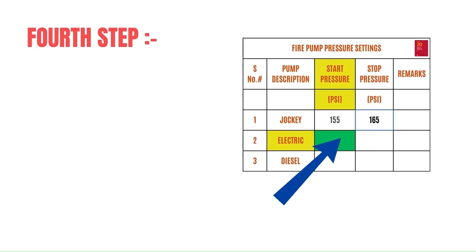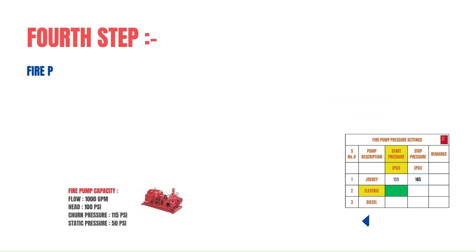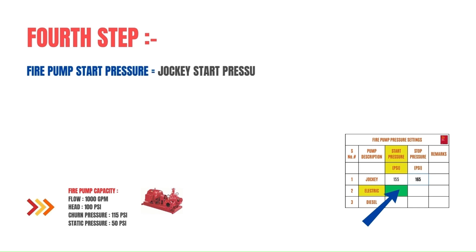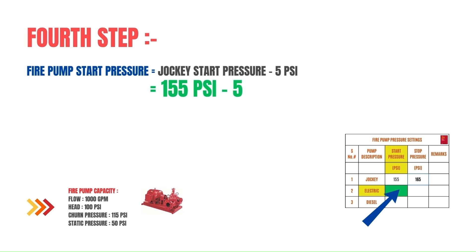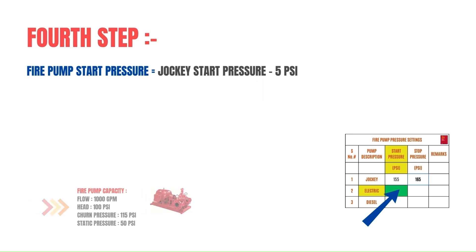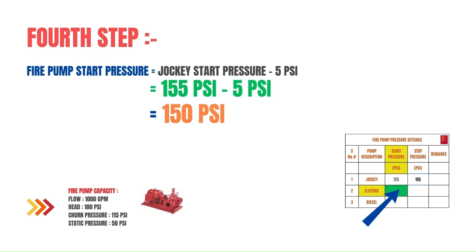The fourth step is very important: calculating the fire pump start pressure, or electric main fire water pump start pressure. It should be 5 psi below the jockey start pressure. So 155 psi minus 5 psi gives us 150 psi.